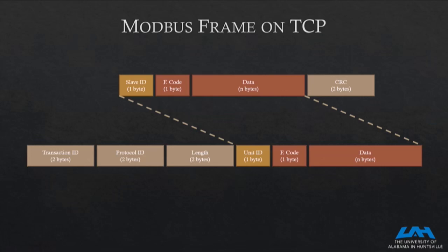Length is length, right? How many bytes there are after it. And after that is just plain serial Modbus frame as it was before. They kept the slave ID byte on that frame because some people will just convert between TCP/IP networks and serial networks, so you have old devices talking serial and new devices talking TCP. Keeping that byte over there means that serial devices will also be able to receive that message, even if they are addressed on TCP. For TCP-only PLCs, usually that byte means nothing - they will accept anything.